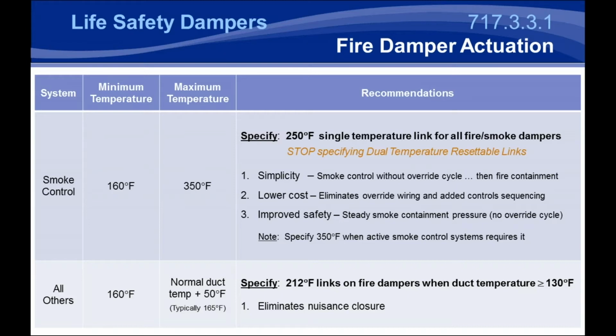Code originally had a requirement that all dampers needed to close within a certain point of heat exposure, and that required a dual temperature resettable link that could be manually overridden by a smoke control system at a control panel. This is no longer a portion of the code, but is still very common, and we as a damper manufacturer like to urge engineers to specify a single temperature link, because that's all that's required for the damper at the highest level that's needed, so 250 or 350 depending on your system.